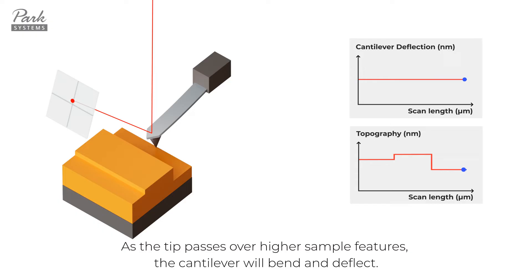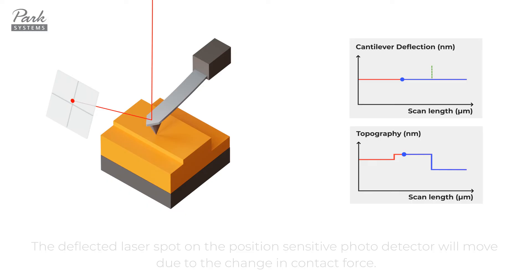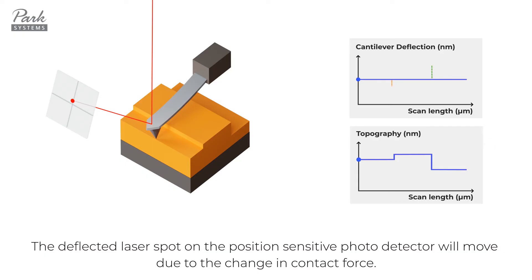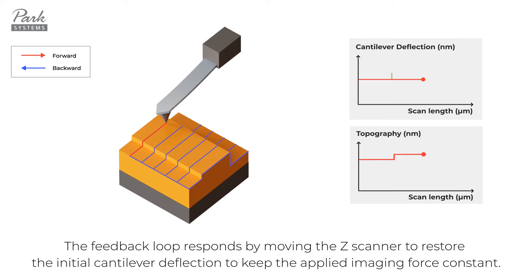As the tip passes over higher sample features, the cantilever will bend and deflect. The deflected laser spot on the position-sensitive photo detector will move due to the change in contact force. The feedback loop responds by moving the Z-scanner to restore the initial cantilever deflection to keep the applied imaging force constant.